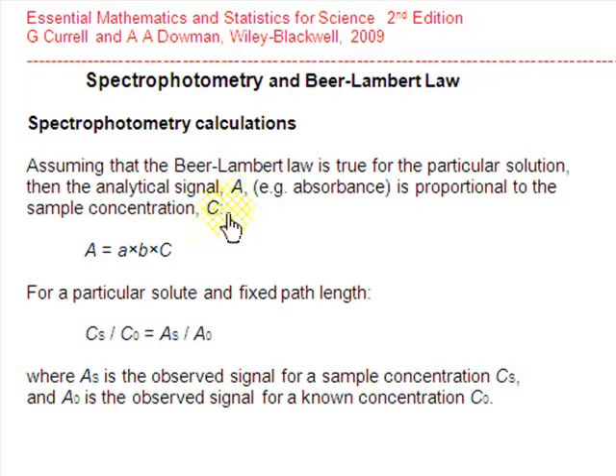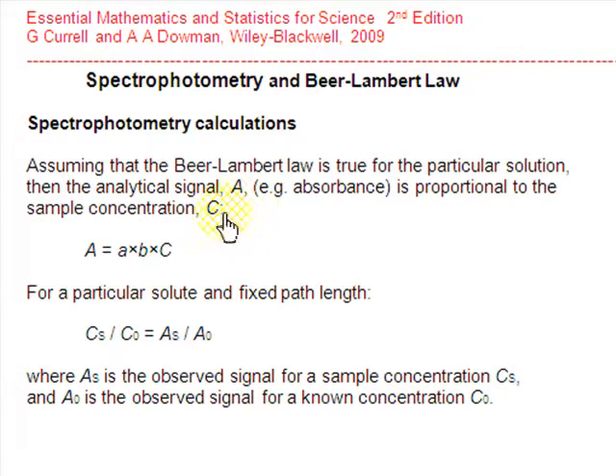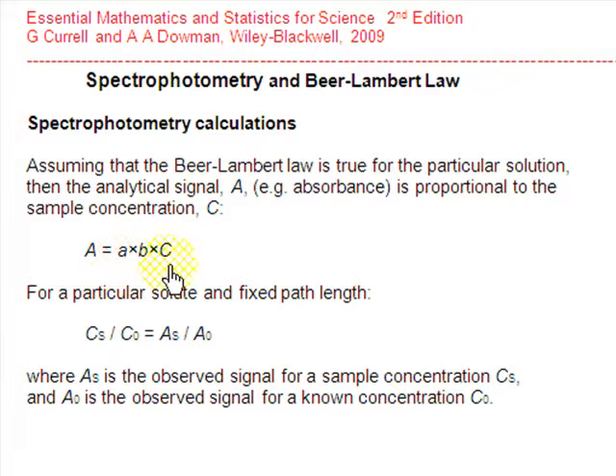In a spectrophotometer, if the Beer-Lambert law is true for a particular solution, then the analytical signal A recorded is proportional to the sample concentration C. This can often be written as the absorbance, capital A, is equal to ABC, where A is the absorptivity of the solute, B is the path length in the spectrophotometer, and C is the concentration of the solution.